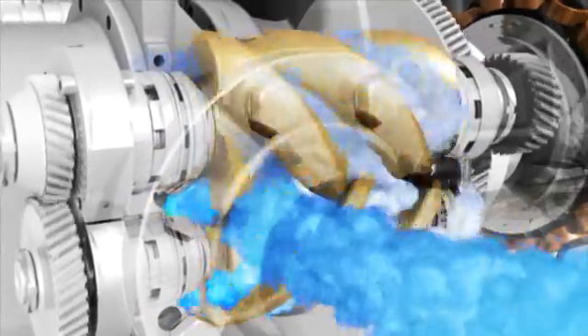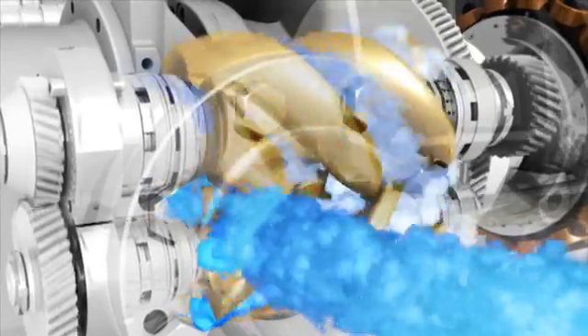Rotor coatings, which enable close clearances, are essential to the reliability and performance of oil-free compressors. Traditional rotor coatings decay with normal use, deteriorating performance and overheating, compromising delivered air quality and jeopardizing sensitive processes and overall reliability. This decay simply means less delivered air, more power consumed and reduced operating life.